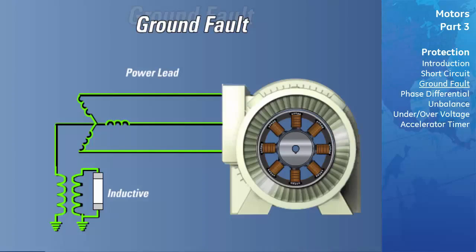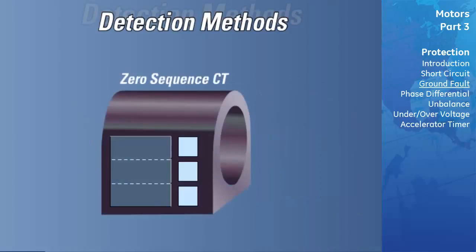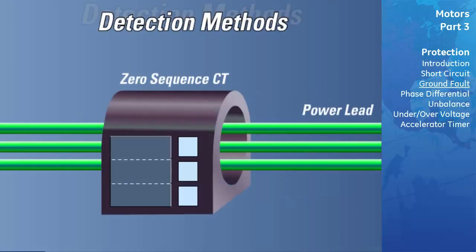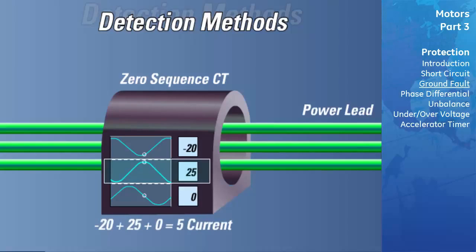There are several ways by which a ground fault can be detected. The most desirable method is to use the zero-sequence CT approach, considered the best method due to its sensitivity and inherent noise immunity. All phase conductors are passed through the window of the same CT, referred to as the zero-sequence CT. Under normal circumstances, the three phase currents will sum to zero resulting in an output of zero from the zero-sequence CT secondary. If one of the motor's phases were to short to ground, the sum of the phase currents would no longer equal zero, causing a current to flow in the secondary of the zero-sequence CT. This current would be detected by the relay as a ground fault.